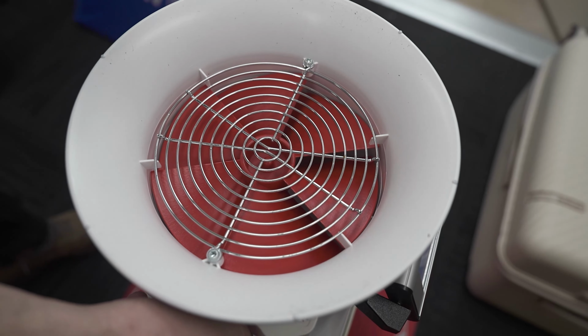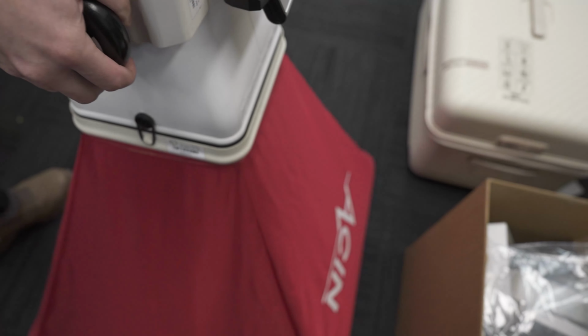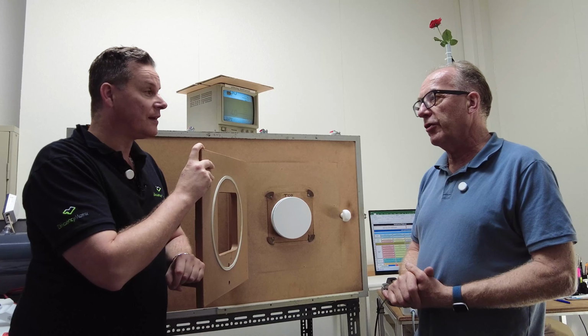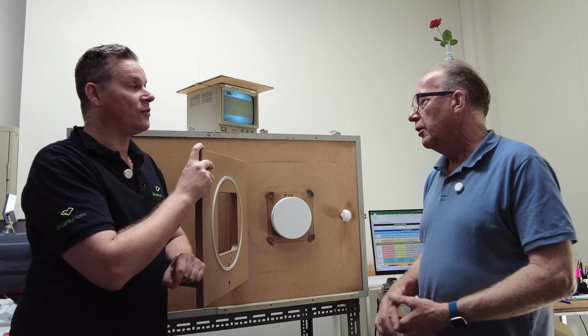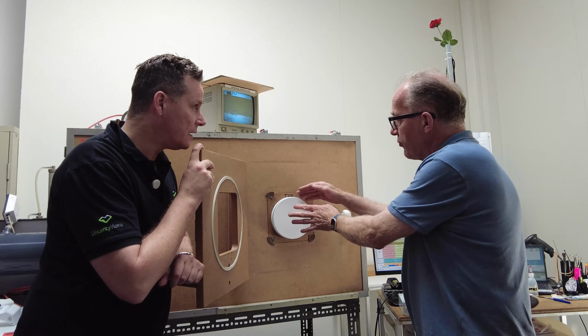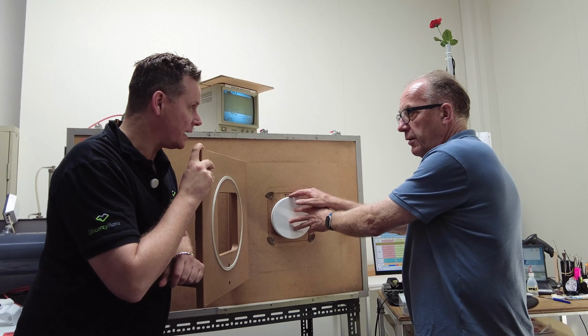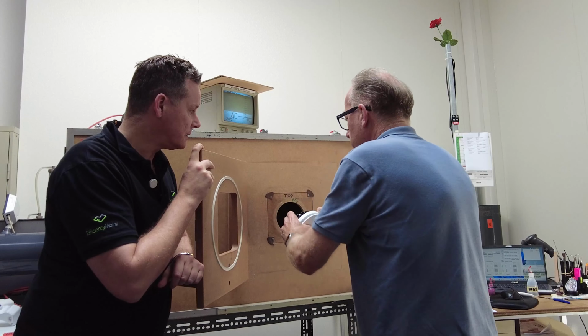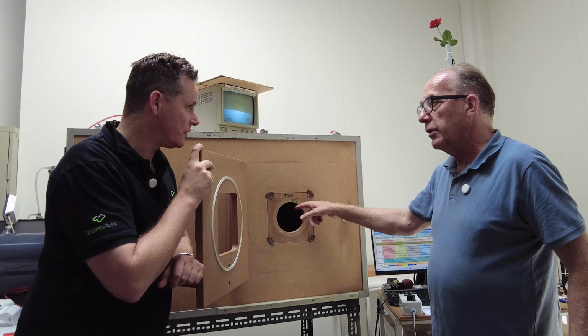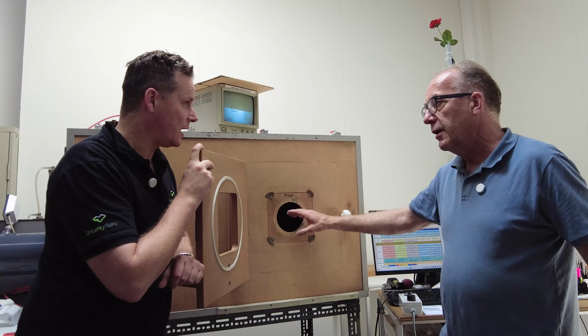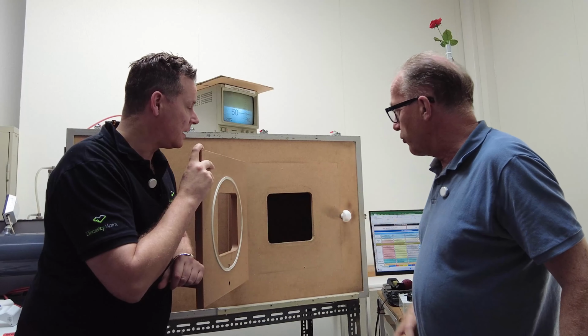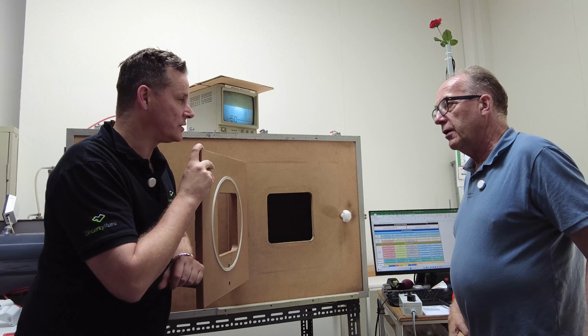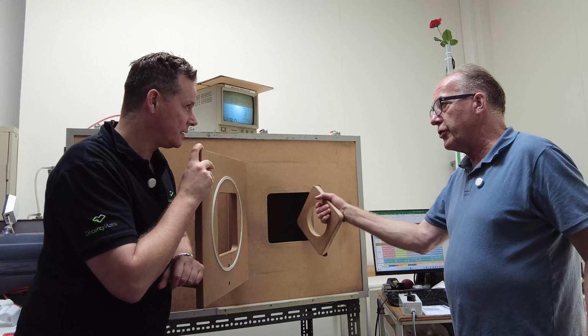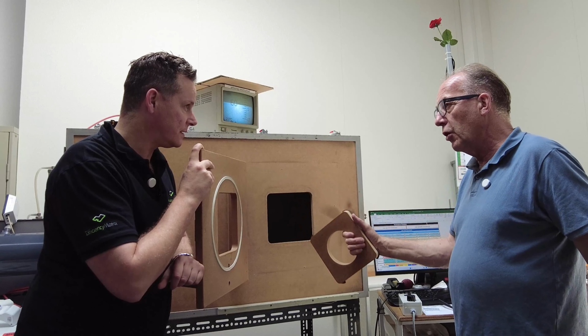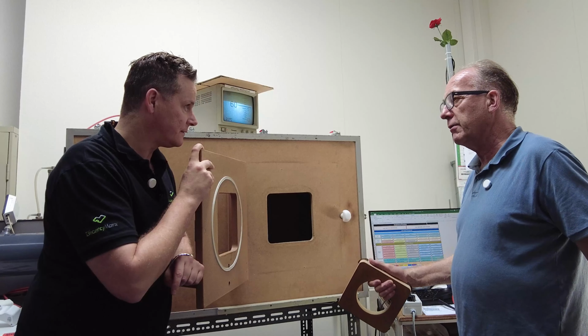It's more important to have the compensation when the resistance of the system is low. Right. Suppose this one, the pressure drop over such a grill is quite high. Yes. Now I'll take it off. The pressure drop over such a hole is very low. Much lower. Gotcha. And the pressure drop over this is even lower. So if you put a passive flow hood on such a hole, an open hole, low resistance, then you get a huge error. Right.